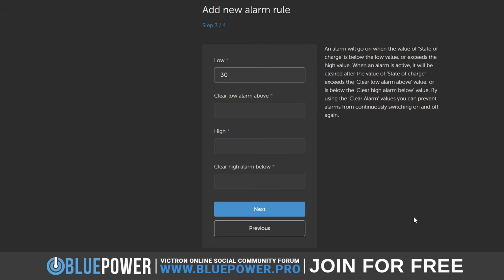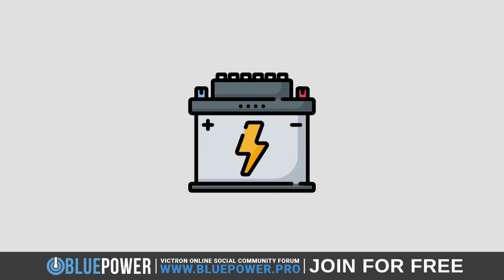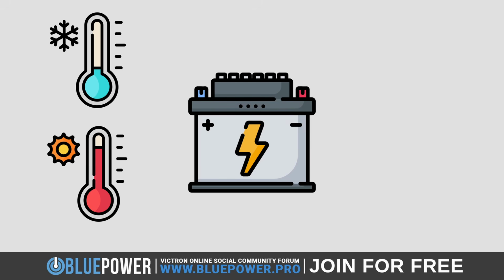Next, we want to enter the SoC percentage above which the alarm should be cleared. I want to create a difference of at least 10% to avoid unnecessary triggers, so I'll set this to 40%. Now we get to the high values, which is where we run into a bit of an issue compared to how temperature works. You see, with battery temperature, it's important to monitor both the lows and highs in order to avoid the battery from getting too cold or too hot.